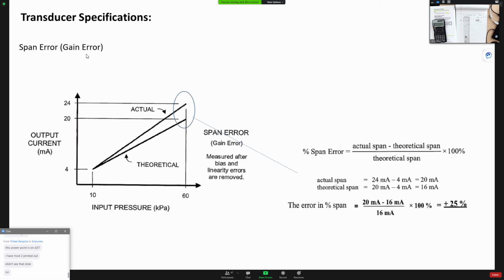Span error. Span error, another name they call the gain error. So your starting point is right. Your minimum value gives you 4 milliamps, but when it goes up, you're supposed to only go to 20 milliamps, but the actual output can reach 24 milliamps. So those errors are across the whole span of this transducer. Those are called span errors. You don't need to worry about how to calculate this span error. The calculation before is what you have to know. Those are just for your information only.